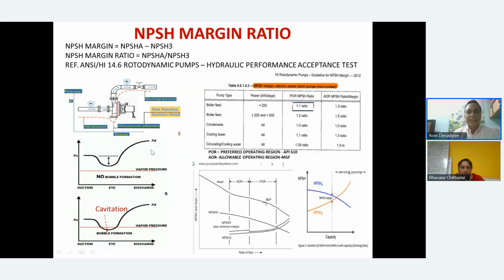Now, what is cavitation actually? Now we have come to NPSH. So why NPSH? What will happen if the NPSH available is not even as much as required? Let us see this. See, this pump has started sucking, so pressure will keep on falling slightly. There is a slight fall because of friction. From here the pressure was up, now it is falling slightly, and then at this point it falls again because there is a direction change. There is a lot of loss happening at the eye of the impeller, and then it is discharging. So at this particular point, there is a fall in pressure.